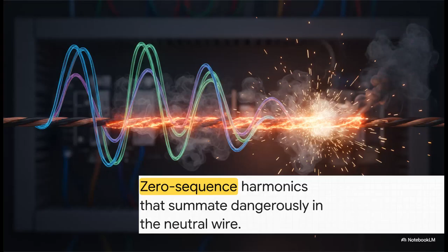Moving on to Section 3, the physical trap, delta transformers. Now, if the grid's natural strength isn't quite enough, engineers actually have to build physical traps to capture this chaos. And to understand that, we need to talk about a very specific, very dangerous enemy: triplen harmonics. These are the 3rd, 9th, and 15th order harmonics. Unlike standard harmonics that naturally balance out and cancel each other across a 3-phase power system, triplen harmonics are what we call zero sequence. They don't cancel out.